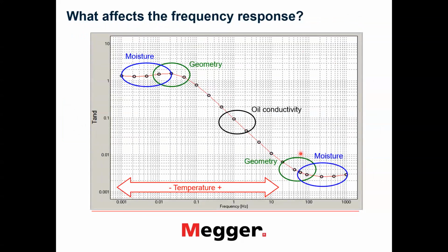And when we started to analyze all this technology, the method, and then what is influencing what, then this picture shows us where we have a moisture influence. It is at high frequencies here, and it is at low frequencies. But then there is an oil conductivity influence at a very large range of the curve, so to speak. And also we have geometry influence in the transformer. And of course we have a temperature influence. If we have a high temperature, then the curve would move towards the right side. If we have a lower temperature, then it will go to the left side.